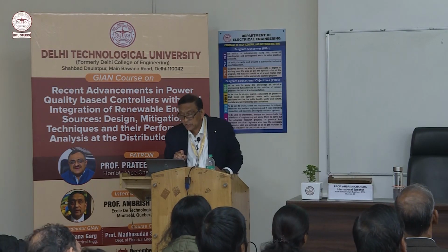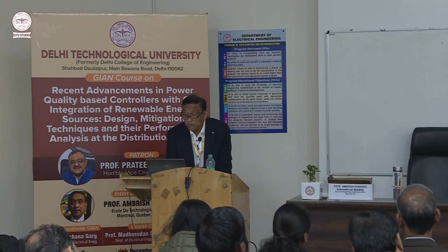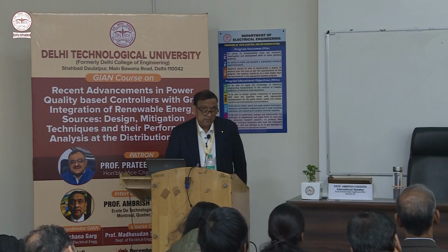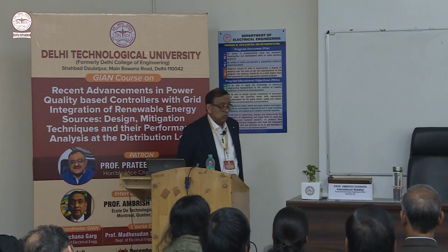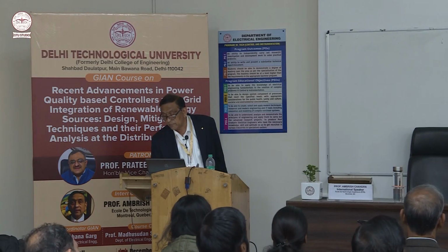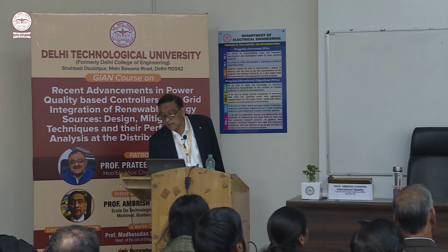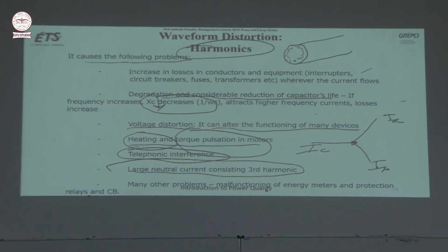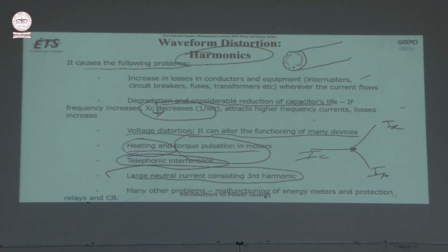Large neutral current consisting of third harmonic. So third harmonic is what? Zero sequence harmonic. So there are three currents coming, ABC, IA, IB and IC. So in ideal condition, the sum of three currents should be zero. But if you have the harmonics, third harmonic is zero sequence harmonic, IA0, IB0, IC0, they are in the same phase. They will not cancel out. The sum of zero sequence harmonic is not zero, it is the sum. Basically, it will increase.